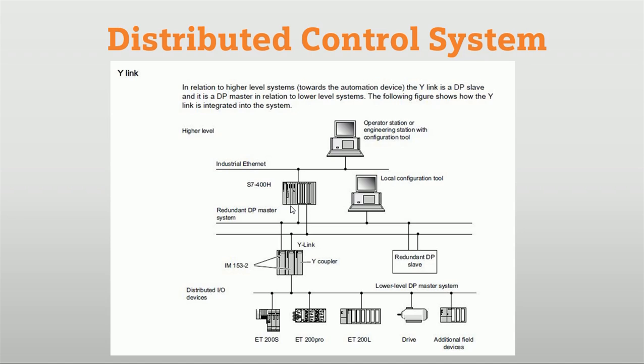Lastly, we have Y-link. The Y-link is used for making redundancy with the communication link. We have the operating station, local configuration tool, and automation station or master control. From the automation station two links are made, connected in a Y-shape. When one communication link or coupler fails, it can carry information via the second cable, and when that cable fails the second link sends data to the automation station. This is how redundancy is made for the coupler and field devices, and even for the automation station itself.